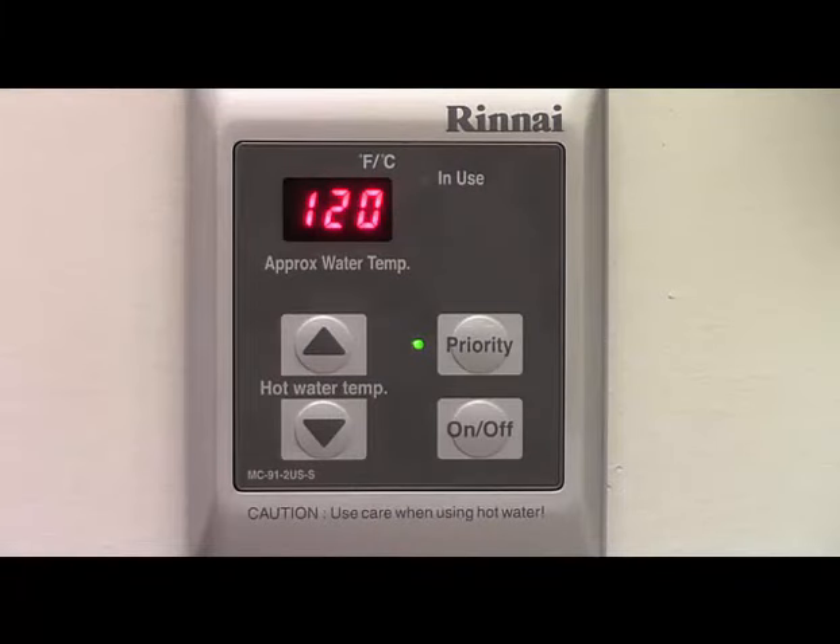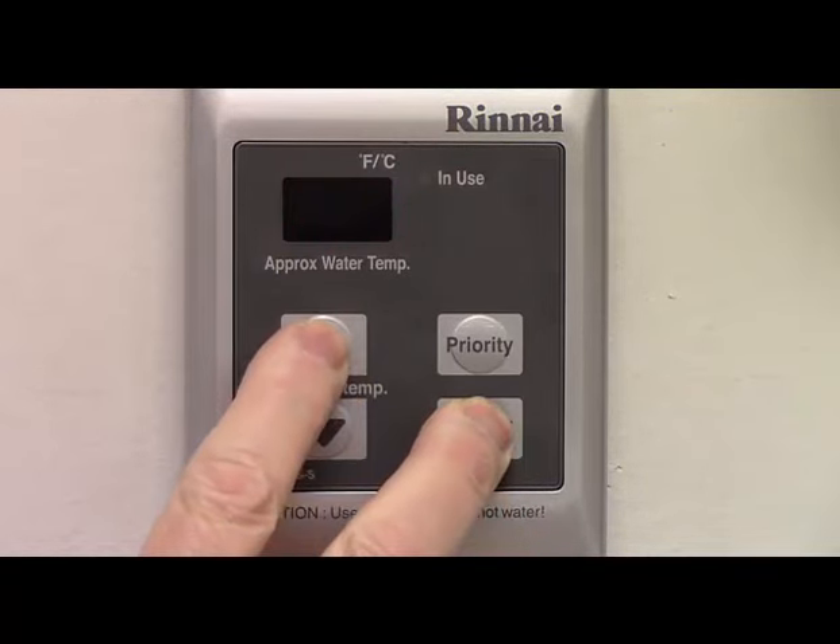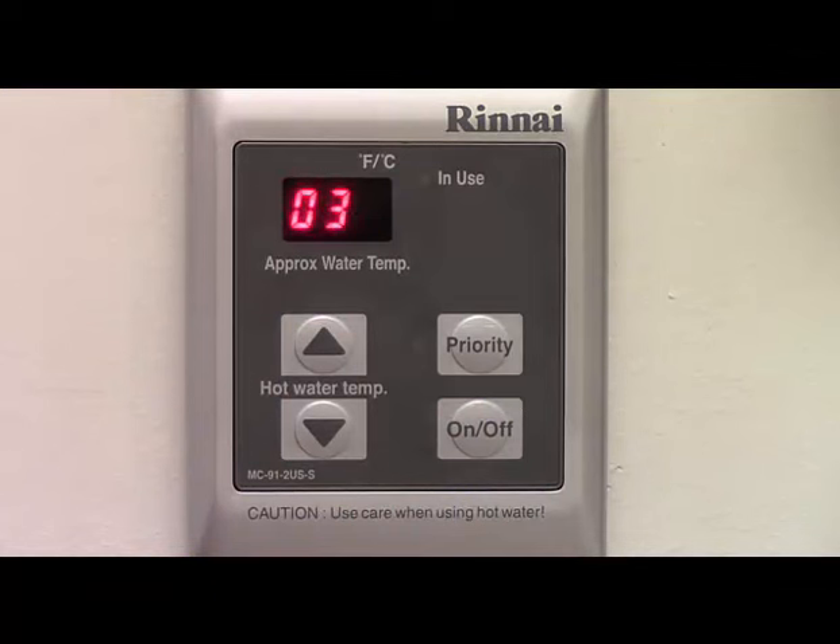The circuit board on the Rinnai tankless water heater can record fault codes should they occur. To access the fault code history, press and hold the on-off button. After two seconds, also press the up arrow, then let go of both buttons. The display will then scroll through the fault code history. First, the fault position will be shown as a single digit, followed by the recorded fault, which will be a two-digit number. Up to nine faults can be recorded, with the most recent code being shown first. Two dashes will be displayed if there are no recorded faults or no fault for that position number.